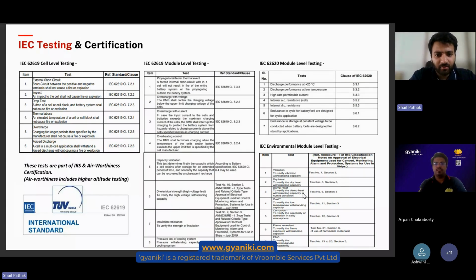In this, the overcharge with voltage test has to be cut off through the BMS. So these tests are all basically for the BMS, apart from one, which is the thermal propagation test. There's also the overcharge with current test and the overheating control test - if the temperature threshold has been passed, the BMS has to cut off the battery system.